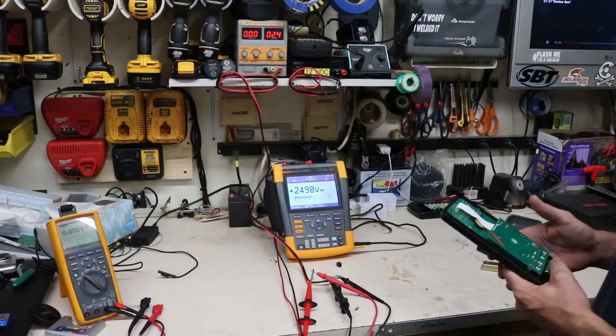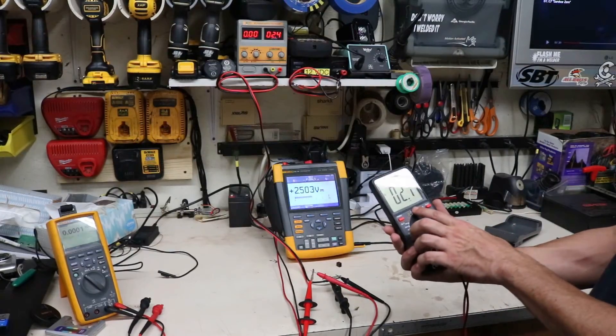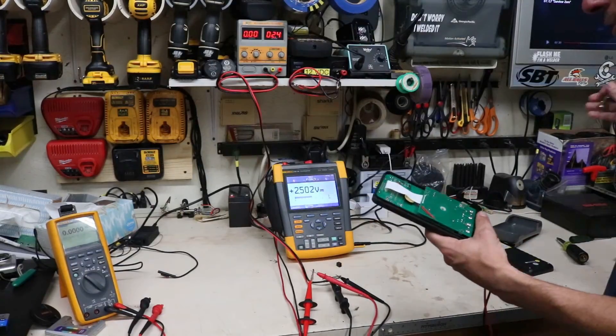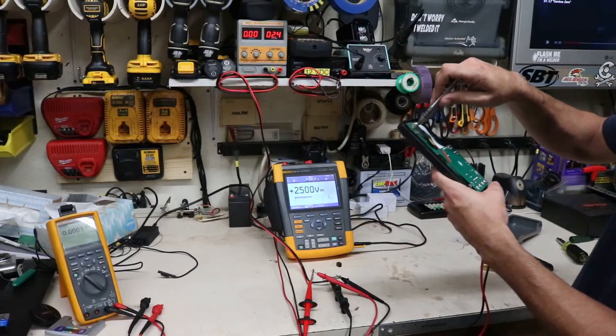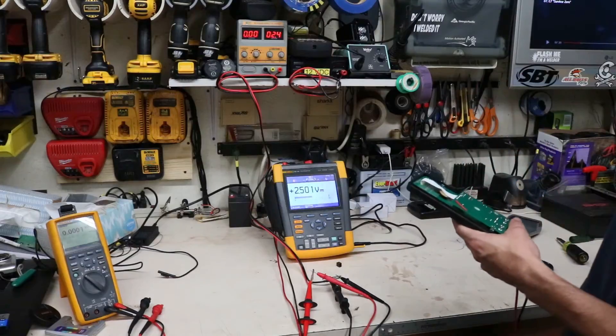About as close as it's going to get, I got it at 2.499. So we show 2.1 on this one. So we're going to take a precision screwdriver and put it in this pot here and rotate it to see if we can get that reading to come up.